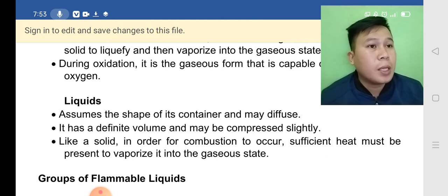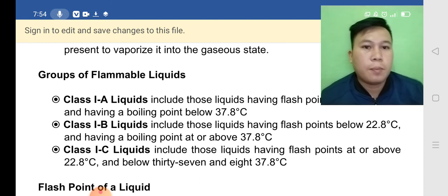Okay. We have groups of flammable liquids. Dito naman, grabe kalawak nung pinag-aaralan natin. So, we have class 1A liquids, which includes those liquids having flash point below 22.8 degrees Celsius and having a boiling point below 37.8 degrees Celsius. So, yan yung class 1A liquids. Class 1B liquids include those liquids having flash point below 22.8 degrees Celsius and having a boiling point at or above 37.8 degrees Celsius. So, makikita nyo. Class 1C liquids include those liquids having flash points at or above 22.8 degrees Celsius and below 37.8 degrees Celsius. So, ang tatandaan nyo lang naman dito is yung boiling point niya at saka flash point niya.